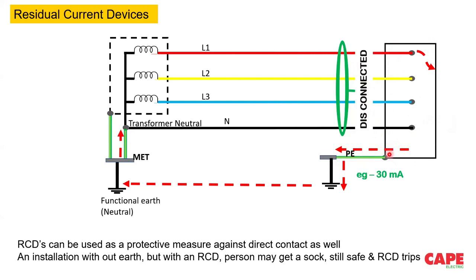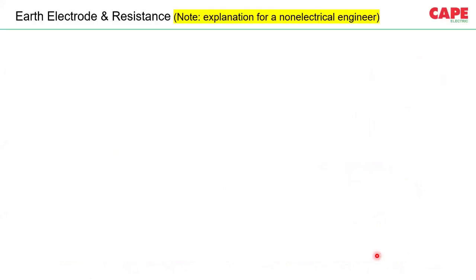Now, the purpose of this earthing and the earth electrode in case of an RCD is, before somebody comes and touches this particular equipment, that means as soon as there is a leakage, your device should trip and keep the installation safer. It means that by making this earthing connection, protective connection, you are protecting the person. So an installation without earth, but with an RCD, a person may get a shock, still safe, and the RCD trips. Very important. So please note that for an ELCB, the mechanism is a little bit different. For an RCD, the mechanism is a little bit different.